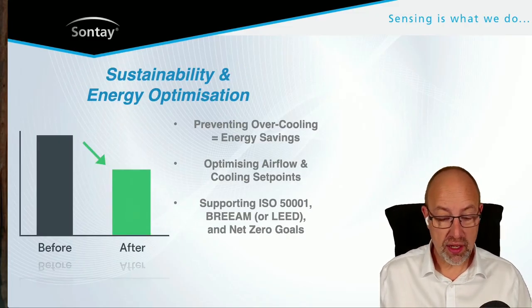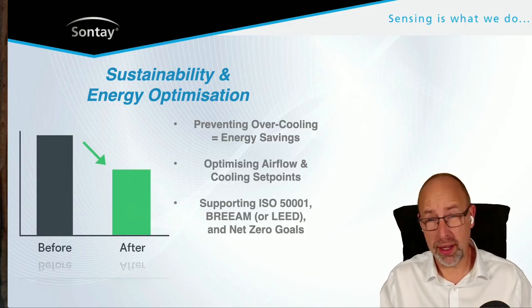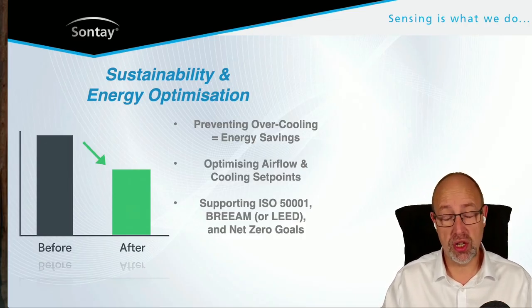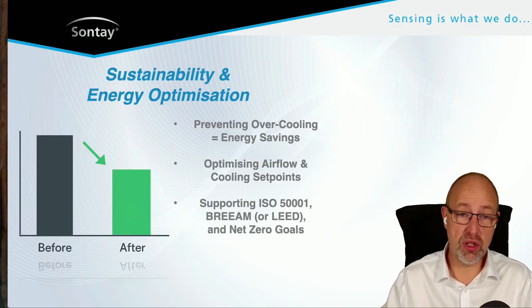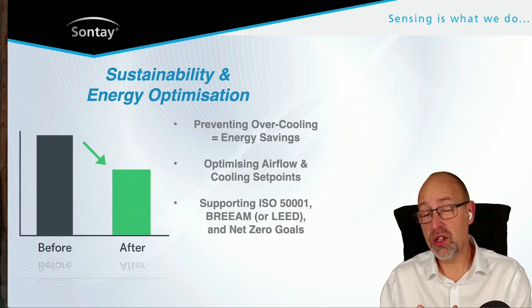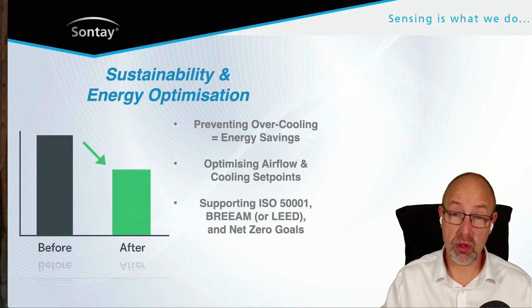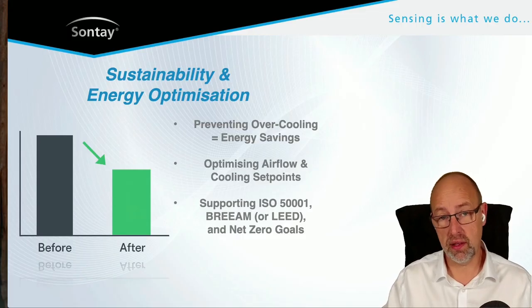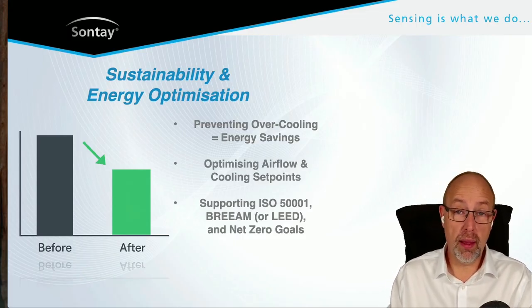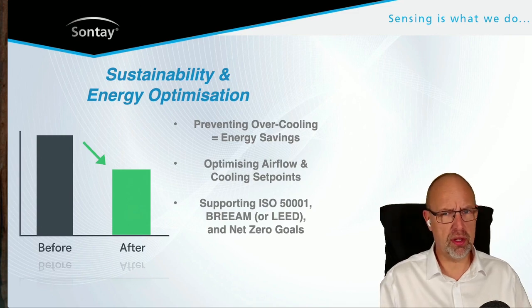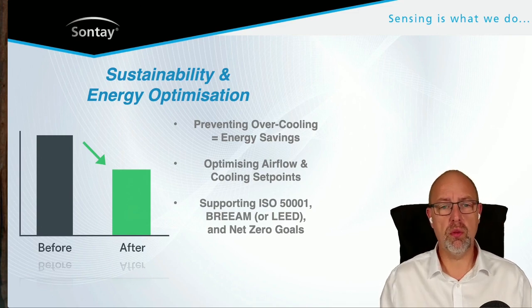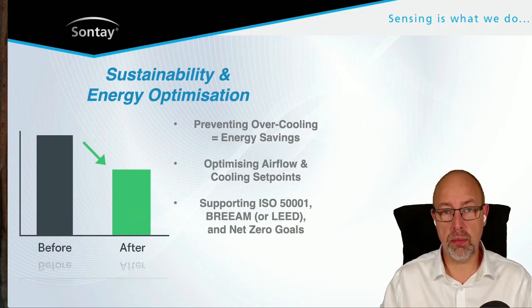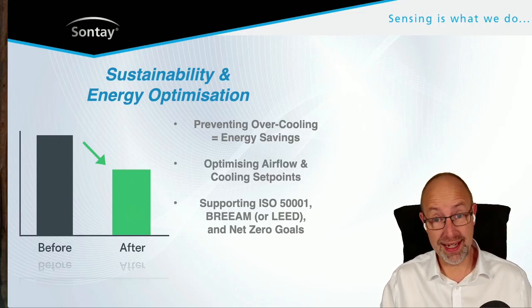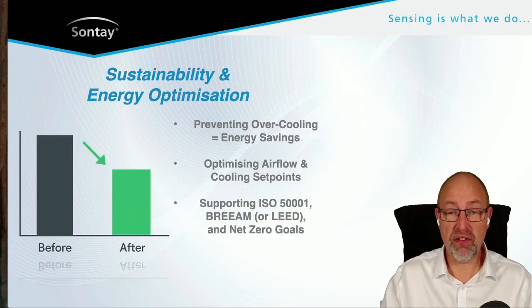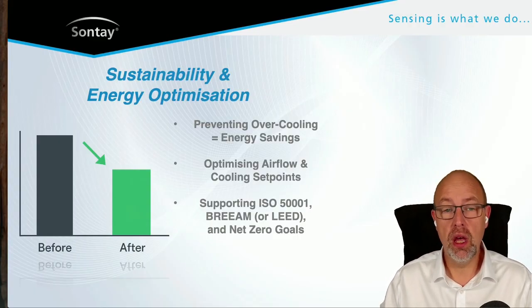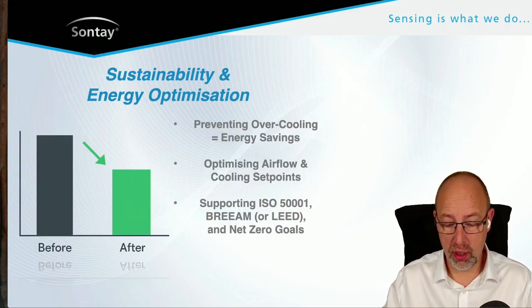For sustainability and energy optimization, if we can prevent overcooling—which is the real big energy issue with data centers—we can achieve energy savings. We can optimize airflow and change cooling set points to match the requirements of the space and equipment without compromising the data hall. We can also comply with things like BREEAM, the Building Research Establishment Environmental Assessment Method, a means of testing the sustainability of a building. This is very difficult with a data center since it's such an energy-intensive process, but you can still meet net zero goals and BREEAM requirements.